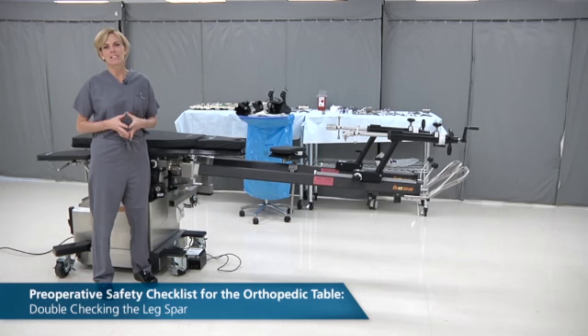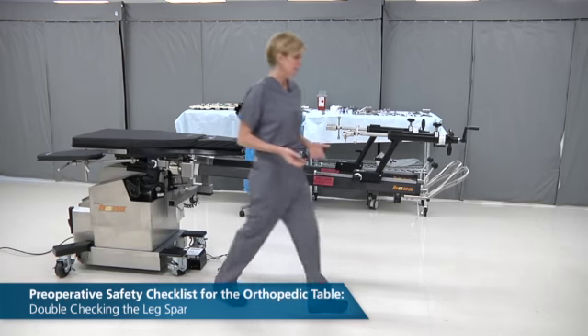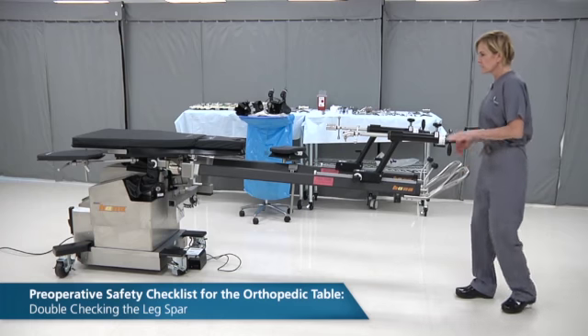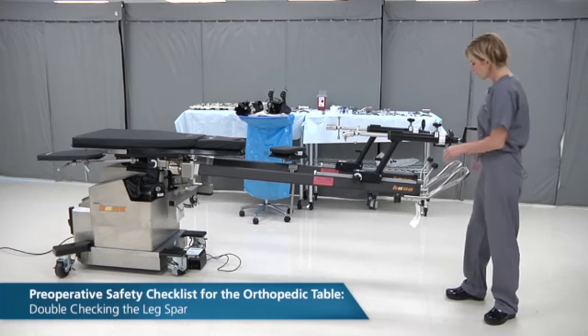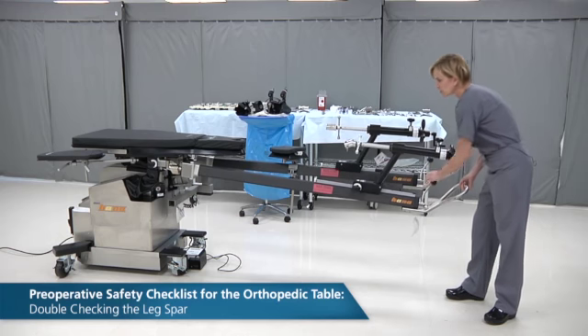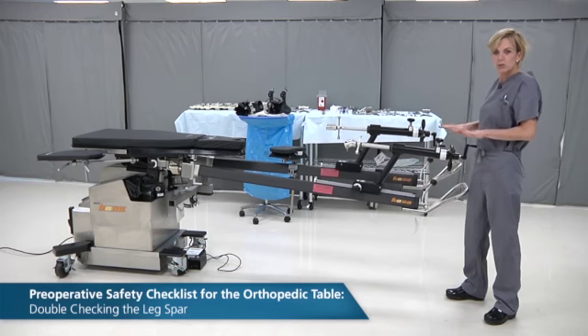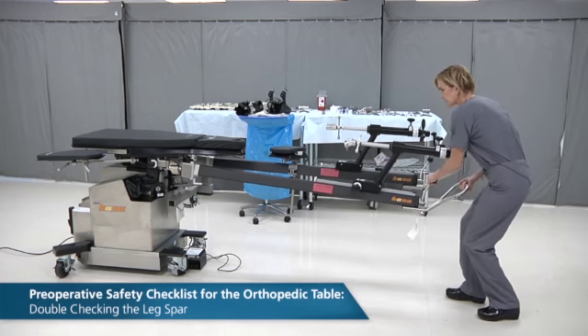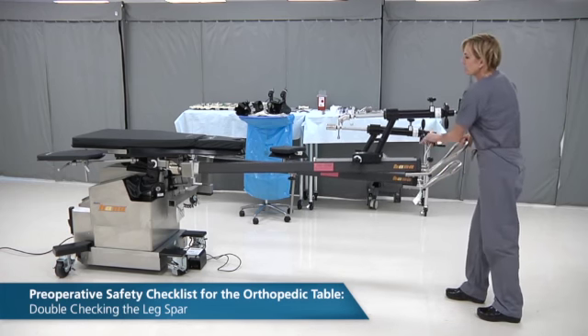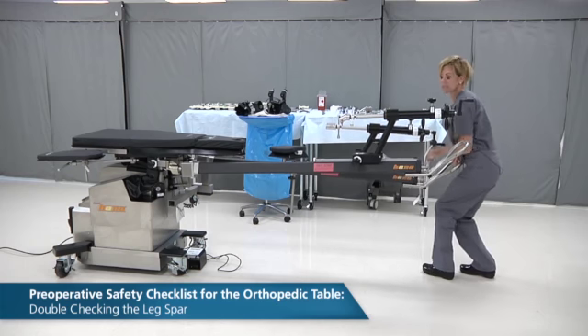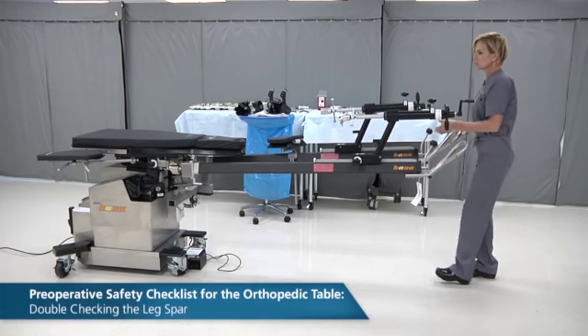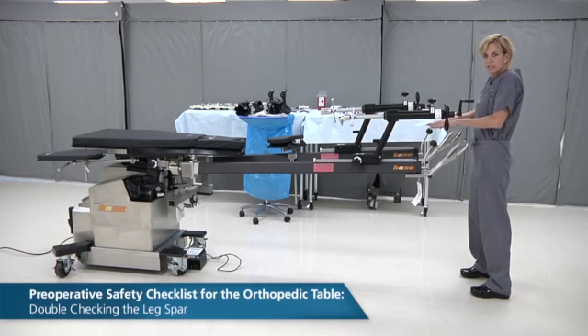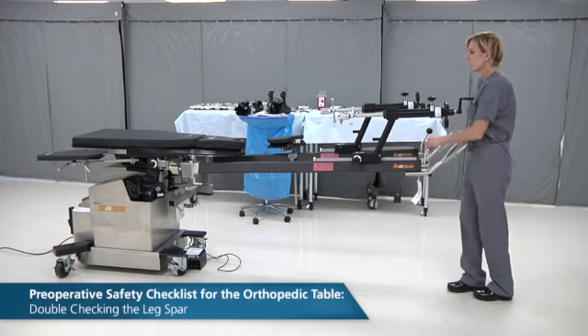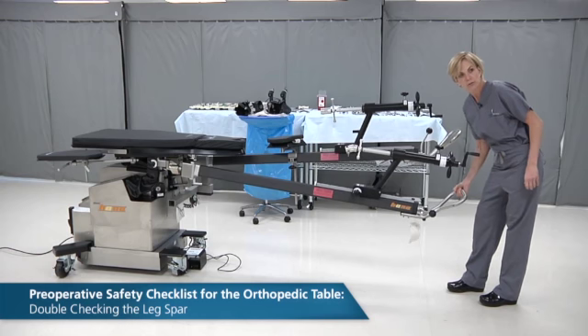The second point of safety for the spars themselves is to make sure that they're positioned appropriately to transfer the patient onto the table. Typically, when the cleaning crew cleans the table, they've moved the spars into a position that's somewhat descended from a neutral position. You want the spars to be at a position of neutrality to accept the patient's feet when it's time to position the patient. So just a little bit of flexion, or at least straight and stable, not at all in an extended position for the transfer.